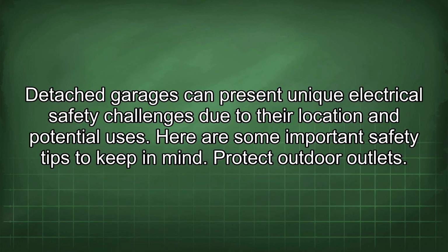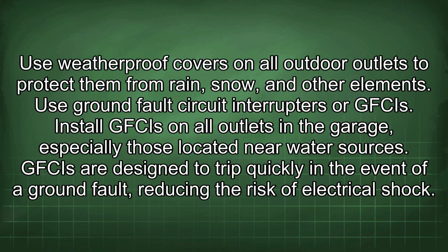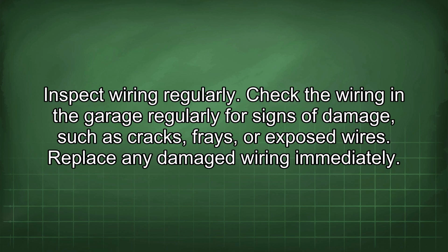Detached garages can present unique electrical safety challenges due to their location and potential uses. Here are some important safety tips to keep in mind. Protect outdoor outlets. Use weatherproof covers on all outdoor outlets to protect them from rain, snow, and other elements. Use ground fault circuit interrupters, or GFCIs. Install GFCIs on all outlets in the garage, especially those located near water sources. GFCIs are designed to trip quickly in the event of a ground fault, reducing the risk of electrical shock. Inspect wiring regularly. Check the wiring in the garage regularly for signs of damage, such as cracks, frays, or exposed wires. Replace any damaged wiring immediately.